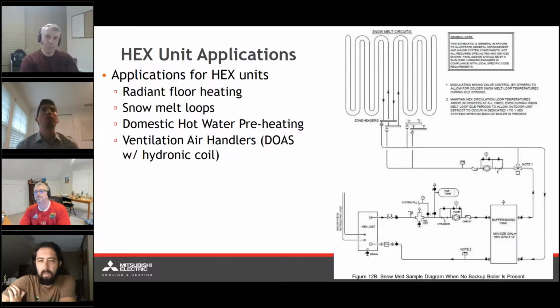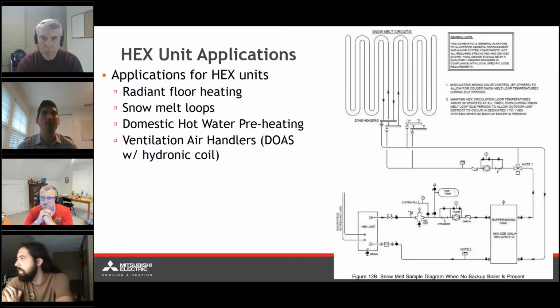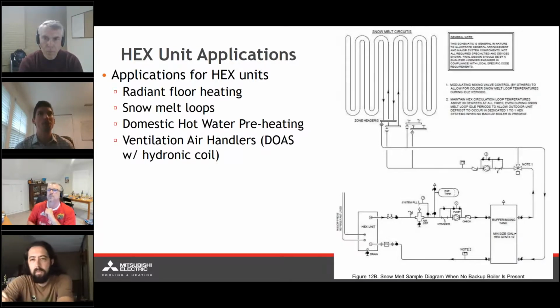So the buffer tanks are going to be required just in the event that the defrost cycle goes long enough, and on a cold enough ambient day, that the water within the HEX unit system runs short of the hot water necessary. So we're going to have a lag time, especially in delivering hot water to spaces that are calling for it, if we don't have that buffer tank. You would be forced into an on-demand hot water heating mode at that point, and the HEX units are not quite designed for that. They're almost there. Let's put it like that. So with that said, we're going to require that for each HEX loop.